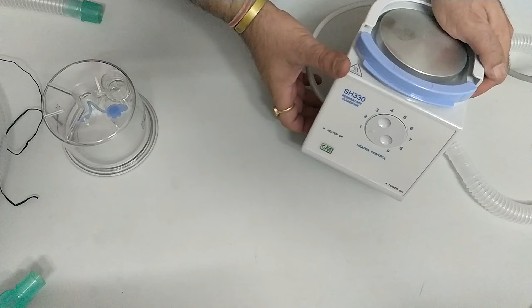Now we are giving a small installation demo on the ventilator. You have to slide the mounting clamp onto the ventilator trolley. Just slide it and it will hang, and then you can power on. Connect the cable to a socket, press the power switch and switch on. You see the heater is on, and both power LEDs are glowing. Now you select the level as per the ambient temperature. You select the heater level so that the patient gets a temperature of 37 degrees plus or minus 1 degree. Now see, the heater starts heating.